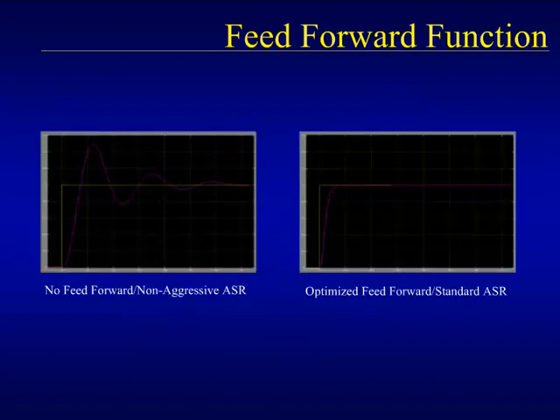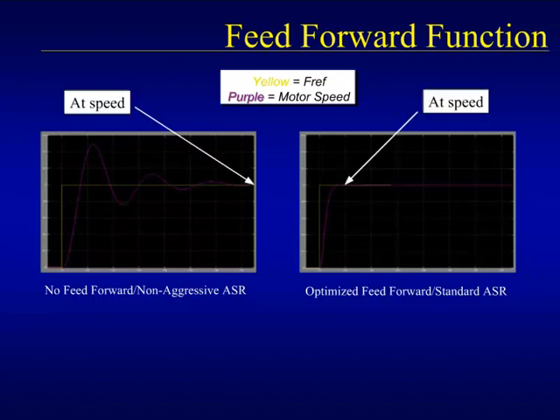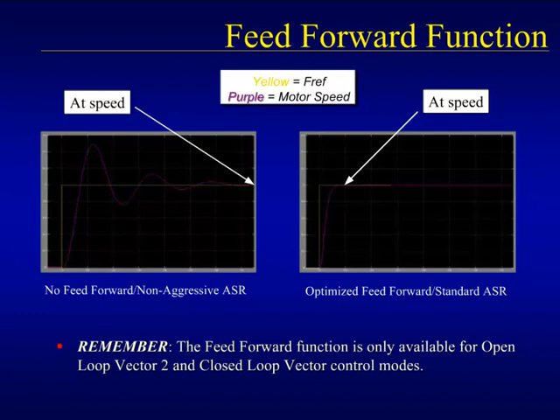These graphs give a better idea of the possible advantages of the feed forward function. On each chart, the yellow trace is the commanded frequency reference while the purple line is the motor speed. The left window shows a non-aggressive, non-feed forward setup — the non-aggressive settings of the ASR are to prevent the overshoot that occurs anyway. The right window shows the feed forward function turned on and the ASR set to factory default settings. The point at which speed agree is met shows a much quicker reaction without any overshoot when the feed forward function is enabled. Remember that the feed forward function is only available while in the closed loop flux vector or open loop vector 2 control modes.